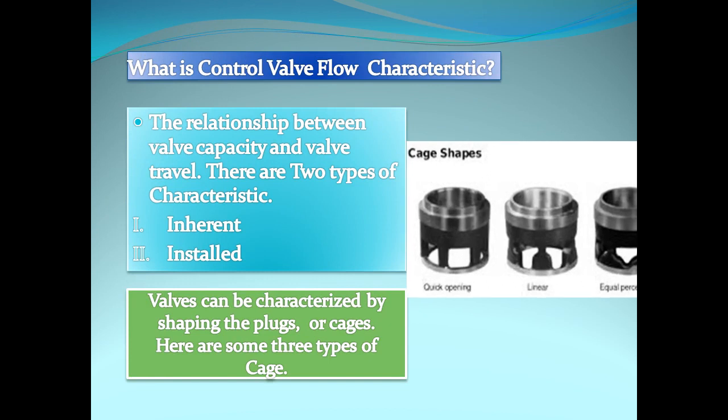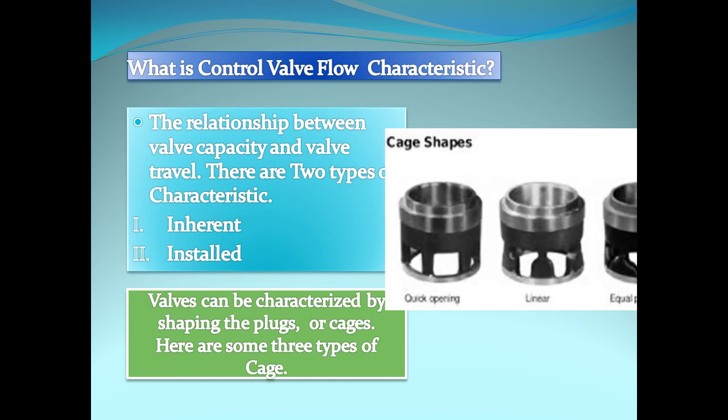What is control valve flow characteristic? The relationship between valve capacity and valve travel. There are two types of characteristics: inherent characteristic and installed characteristic. Valves can be characterized by shaping the plugs, or cages. Here are three types of cages: quick opening, linear, and equal percentage.